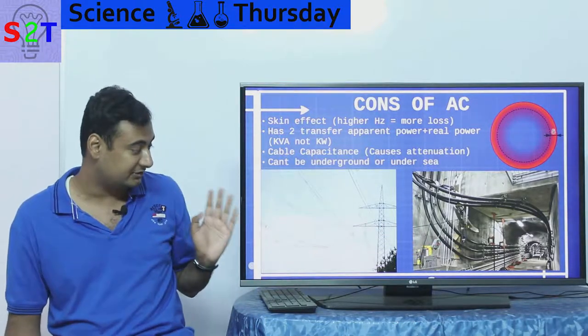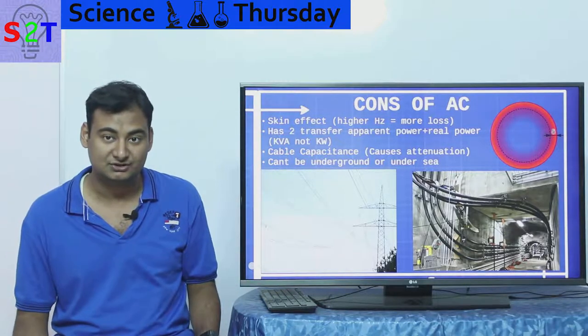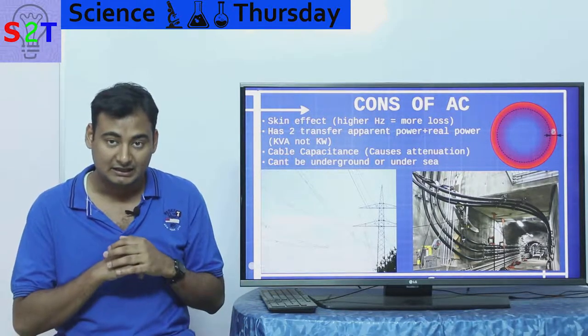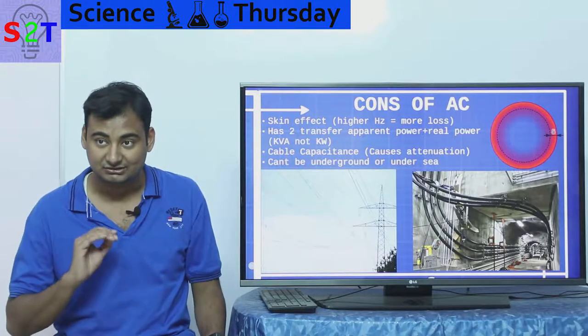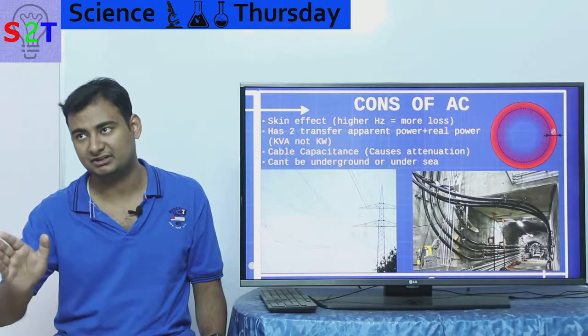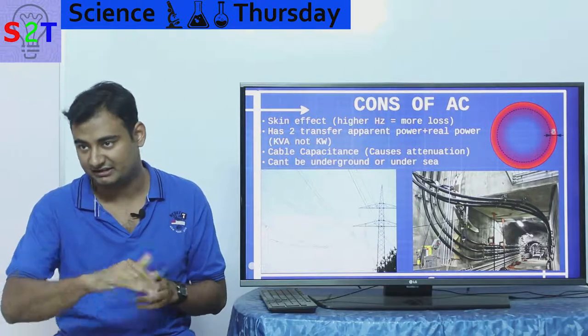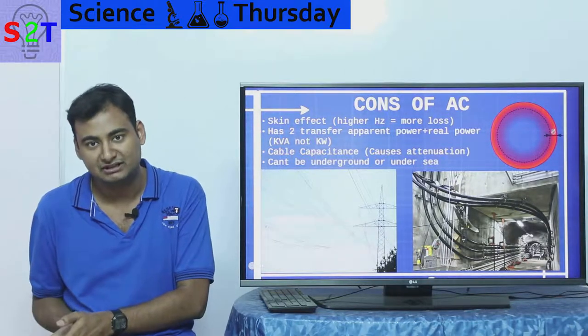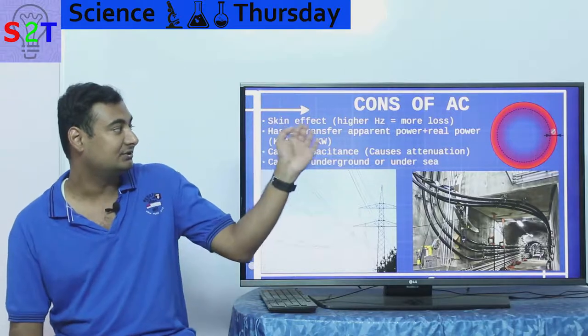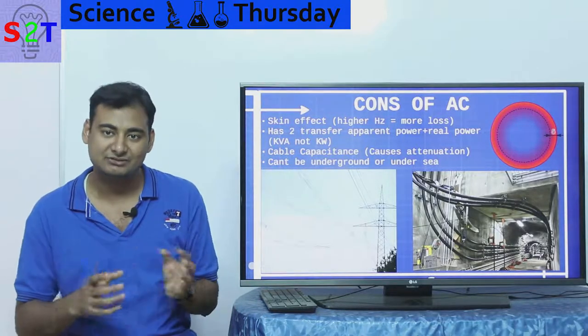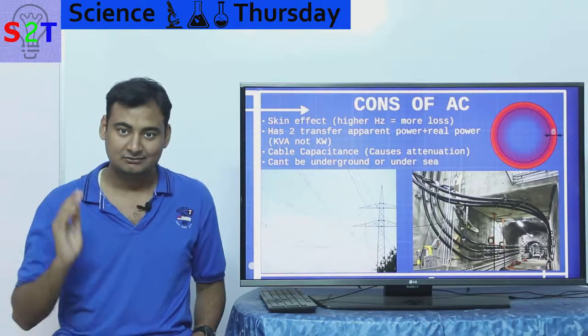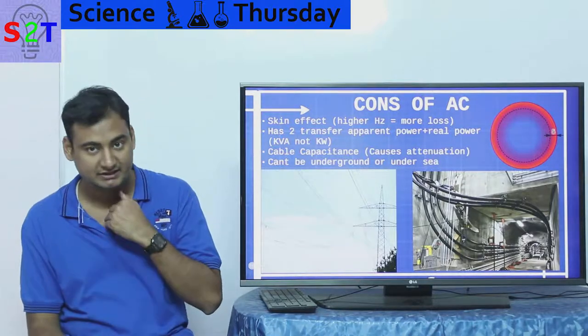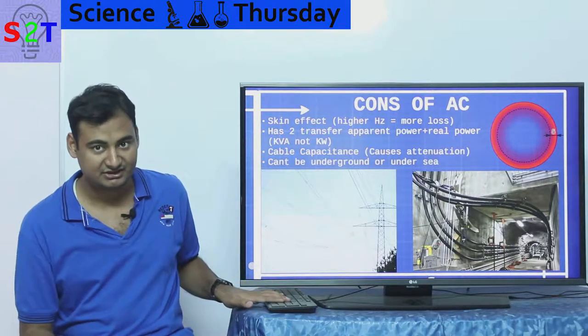Low power underground is not an issue, but if you want to dump high voltage AC lines underground you might be wasting an enormous amount of power without realizing it. And if you're doing undersea, forget anything above 30 kilometers — you simply cannot send AC power more than 30 kilometers undersea. Now this is not an absolute limit; you can reduce the hertz to reduce the skin effect and apply some mitigation, but generally speaking at 50 or 60 hertz, 30 kilometers is your limit.